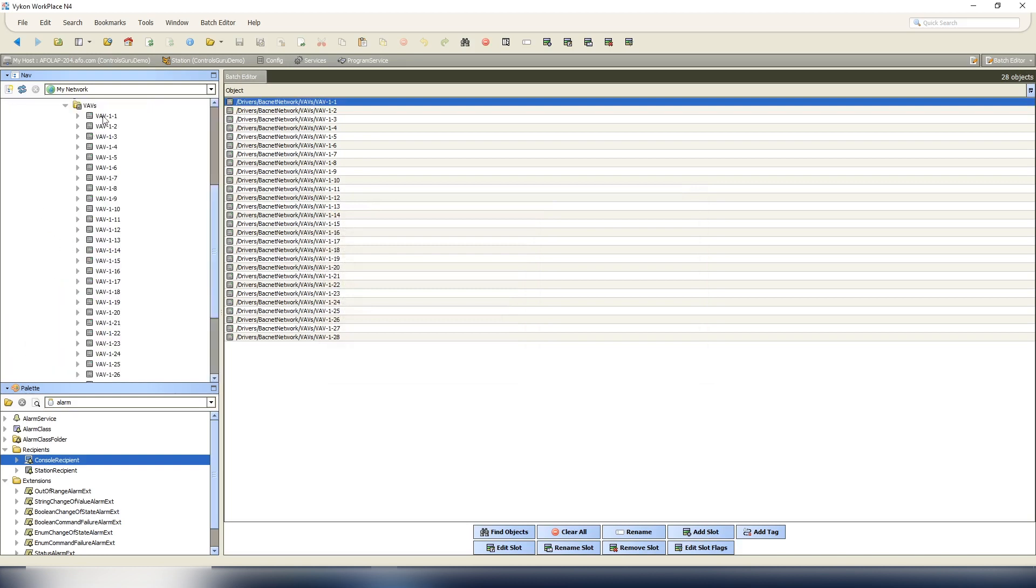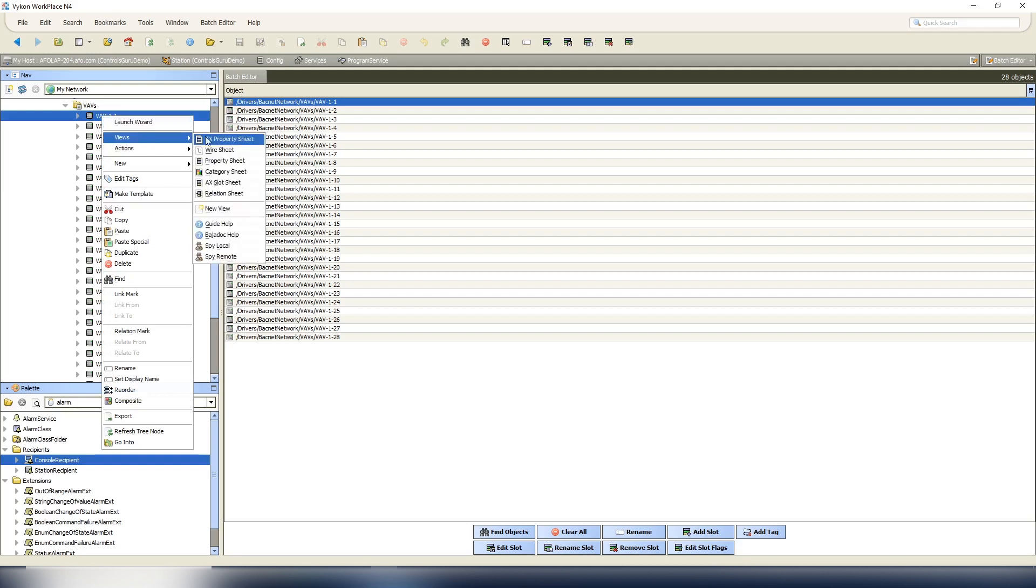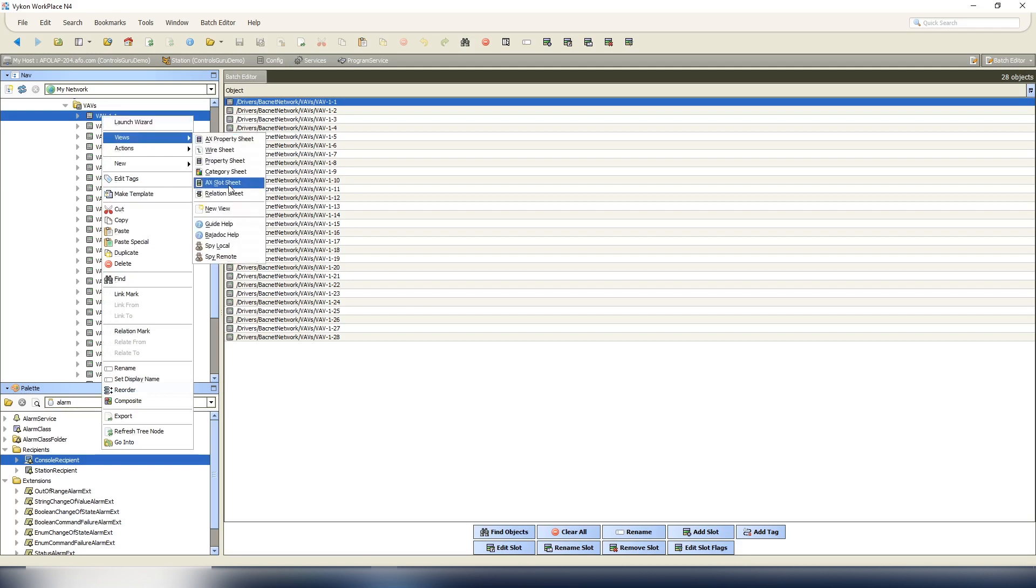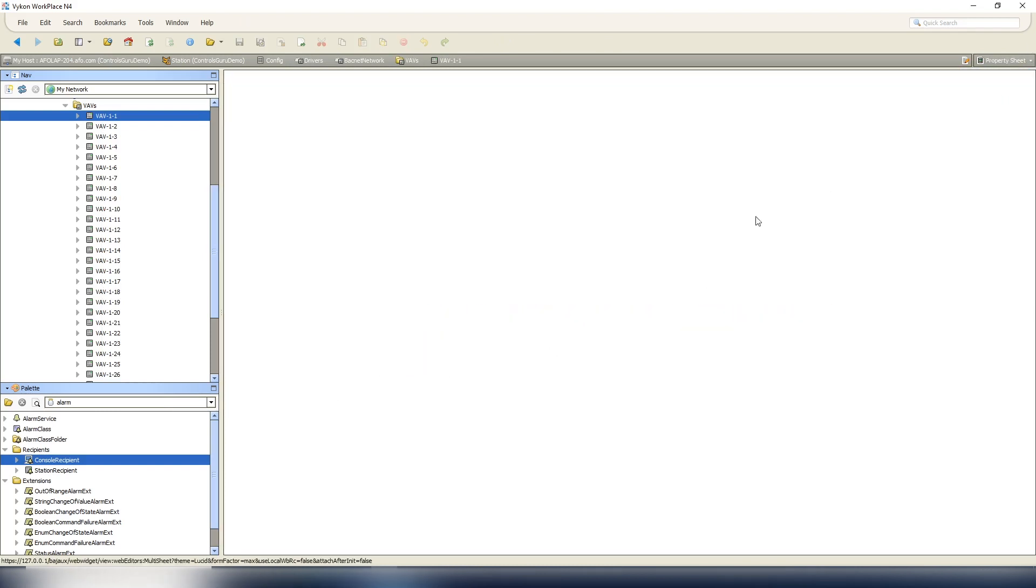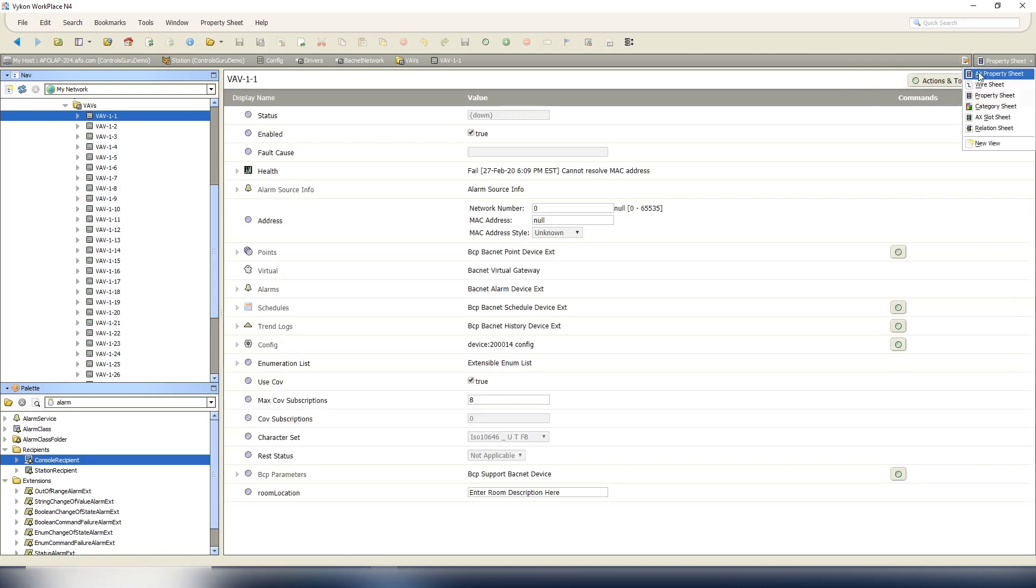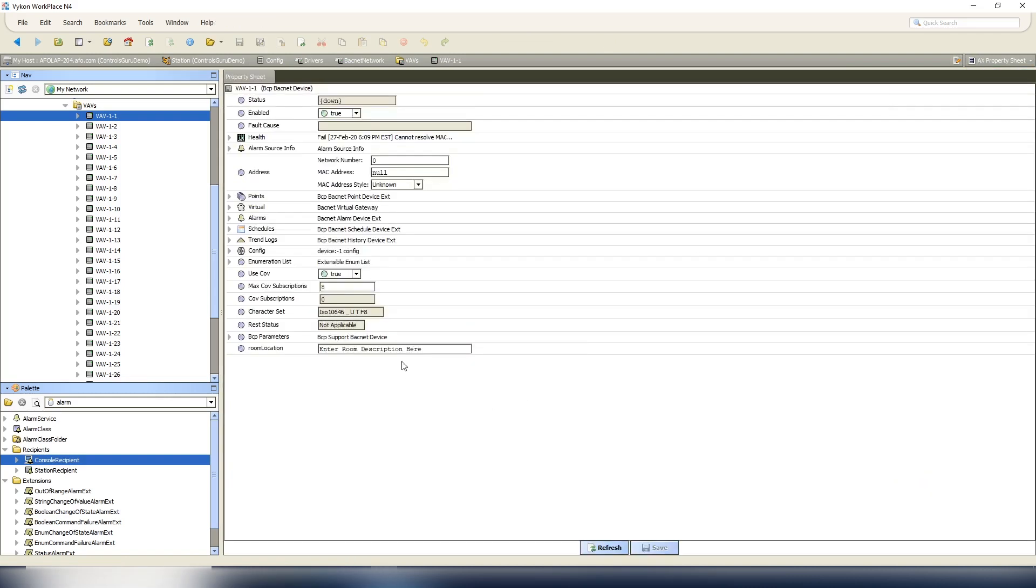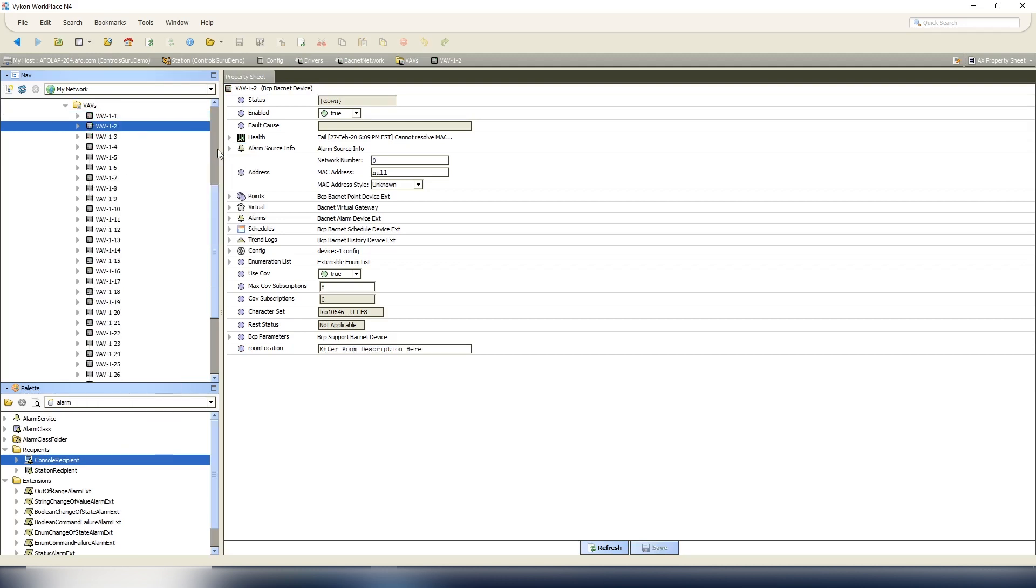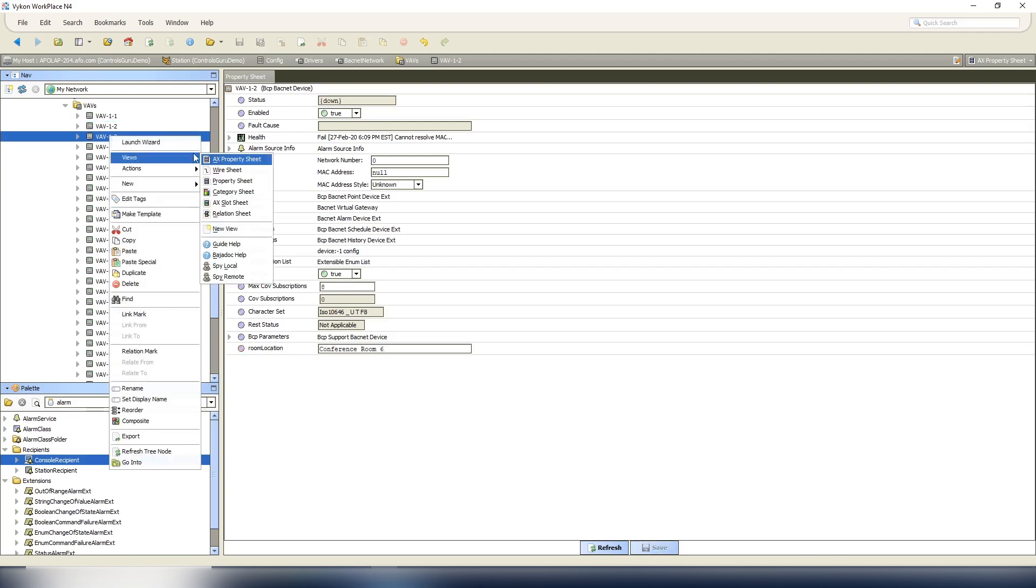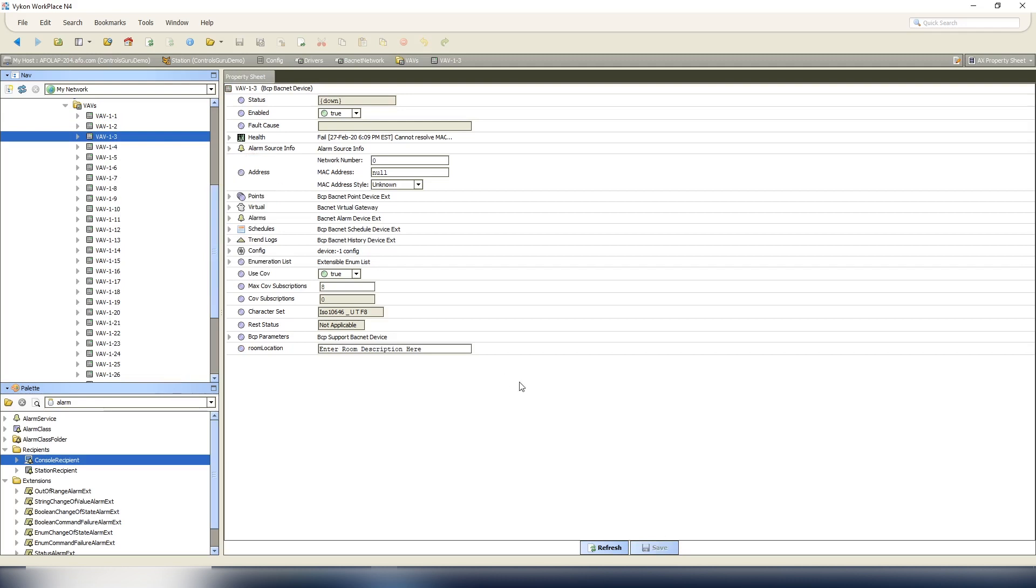Hit okay, get our confirmation. Now if we collapse our services, open up our BACnet network, go to our VAVs, if I open up the slot sheet of a VAV, you're going to see the slot was added - that room location Baja string. Now if we view the property sheet, the AX property sheet, here's our enter room description here. So for this room, this is just obviously a demo so we're going to make random things up. We're going to call this office 101.